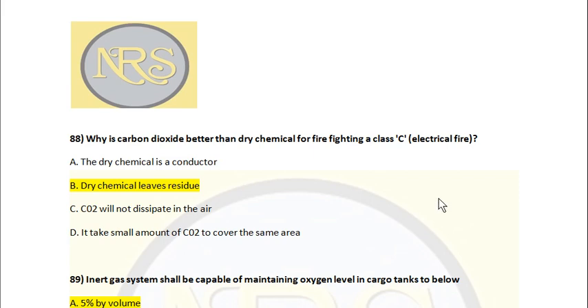Option B, dry chemical leaves residue, is the correct answer for question number 88. When you use dry chemical on an electrical or electronic fire, which mostly involves PCB boards, the dry chemical leaves residue on that region which cannot be repaired—the PCB board has to be replaced. So it is not recommended for Class C fires. But if you don't have a CO2 extinguisher, you can use a dry chemical extinguisher instead. That's the reason for not using dry chemical as the first option—if available, preferably use CO2 rather than dry chemical. So for question number 88, option B is the correct answer.